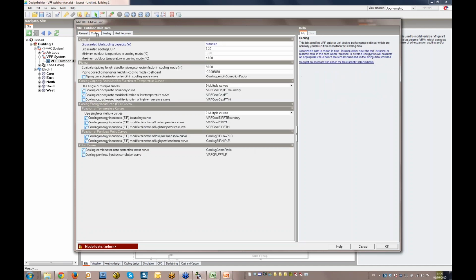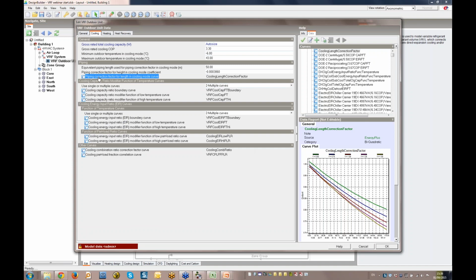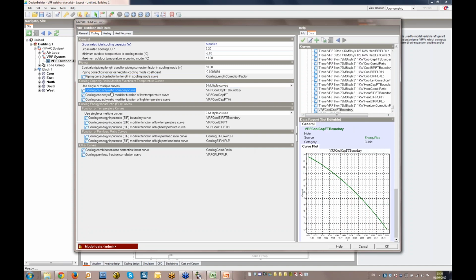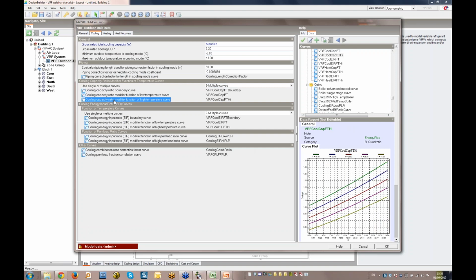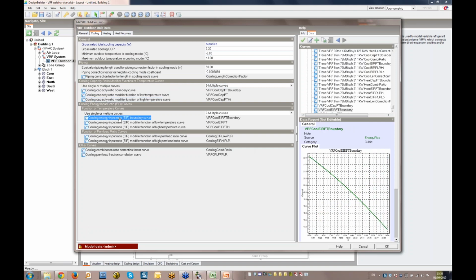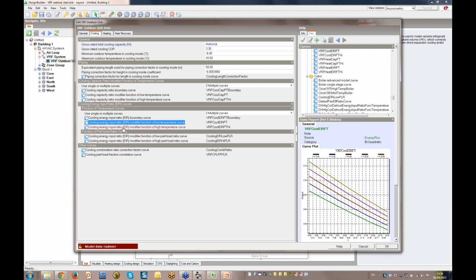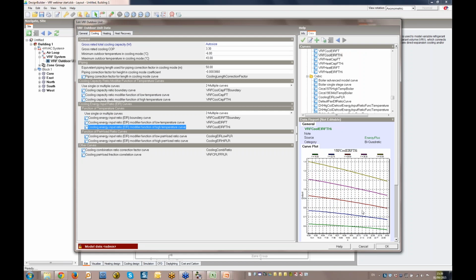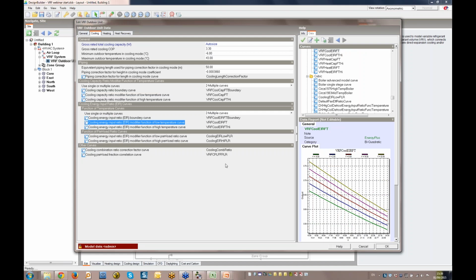Going to the Cooling tab, I can access the cooling specific data such as the rated capacity and COP, amongst other things. No doubt you'll by now have noticed the number of curves. To model a VRF system accurately requires the use of a number of curves to determine performance at each time step, and these differ for heating, cooling and heat recovery. You'll see a visual representation of the curves here at the bottom right of the screen, which can help you make sense of what's going on, rather than just seeing a bunch of coefficients.